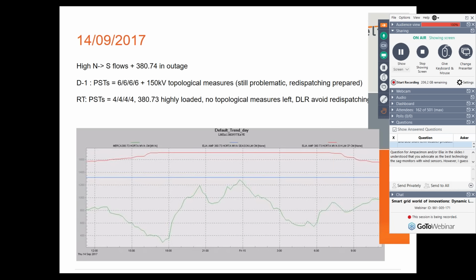It's international redispatching. And thanks to Ampacimon, you see it on the graph. You see in green the loading of the critical line. You see in the night that the lines were really close to the blue horizontal line, which is the static rating, which means automatically that if there were an incident on the grid, after the incident it would overload the line. You see it's so close to the static rating that, of course, the N-1 was not covered with the static rating. But thanks to Ampacimon, you see the red curve, and you see also this beautiful effect that you have more margin in the night than in the day, and so the red curve was really capped at 30%. That's the rule I just explained.